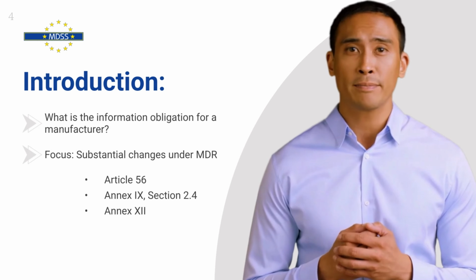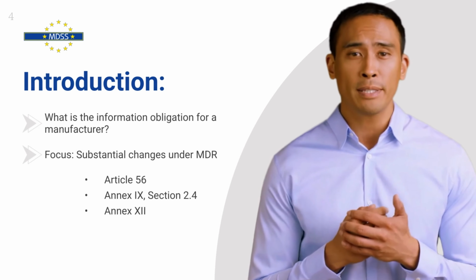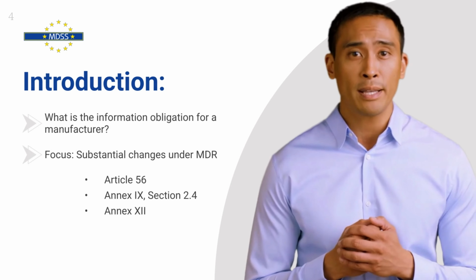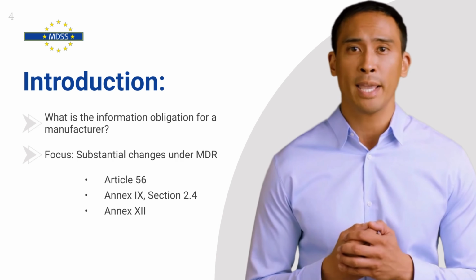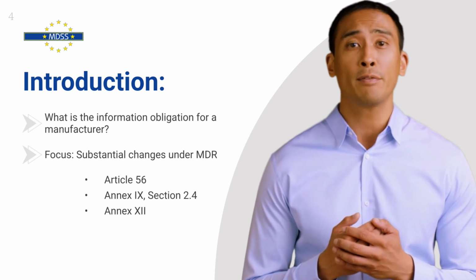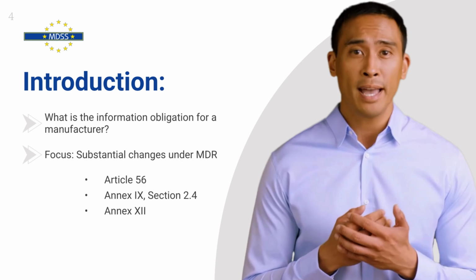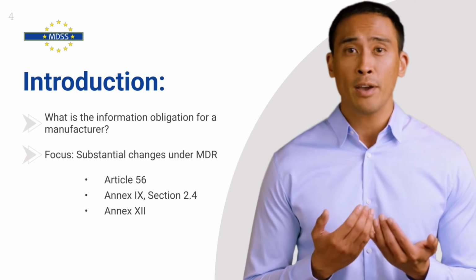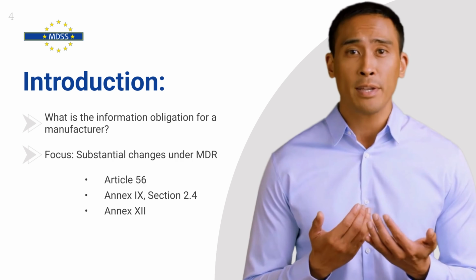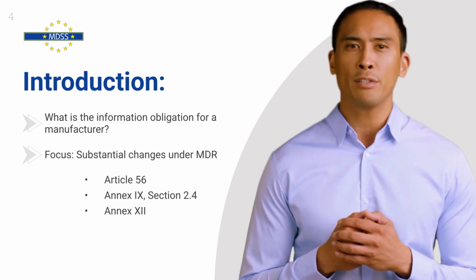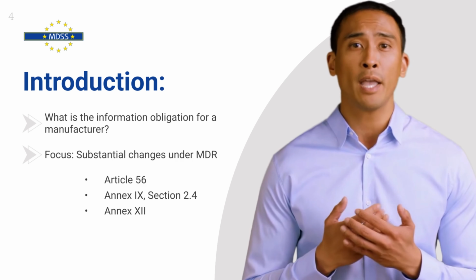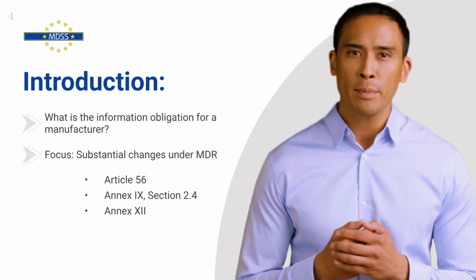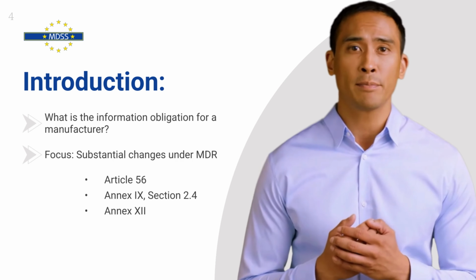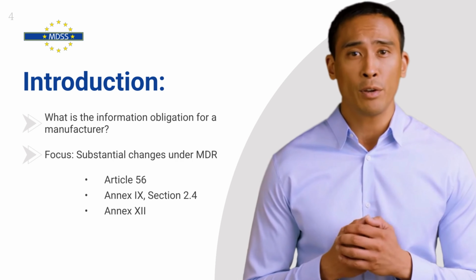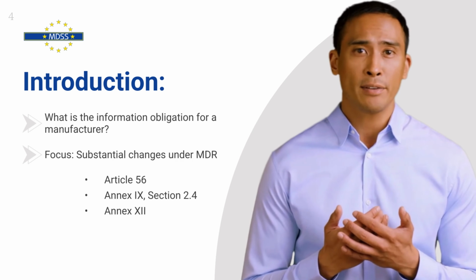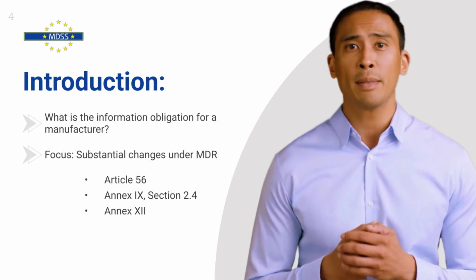What does substantial mean? A closer look at the obligation. There has been considerable discussion around the interpretation of the term substantial under the MDR. A wide range of views exist, often pointing out that the regulation does not explicitly define the term. As a result, it is frequently claimed that the MDR leaves room for broad interpretation. The current practice often results in the notified body being treated as the primary authority on whether a change qualifies as substantial. This is reinforced by procedural expectations in which documentation is submitted for that purpose and determinations are issued accordingly.